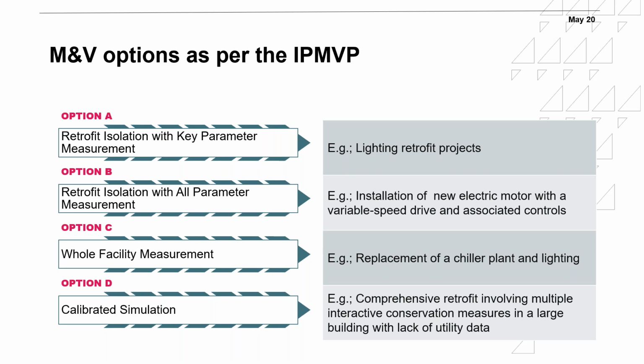Also, option D, if you've done any LEED projects, normally you would use option D for measurement and verification for LEED. In that case, basically, you would create a model normally during the construction of the project. And once the building is occupied, you start gathering data after occupancy, preparing the computer simulation to be calibrated. So you have, let's say, 1 year of consumption. You go back to the model, you calibrate it based on the gathered data. Compare it to the actual consumption now. Once you calibrate the model, then you create another model removing the efficiency measures, and then you compare it to the baseline, saying that without the efficiency measures, this is the consumption.